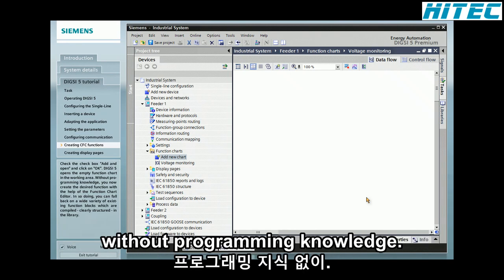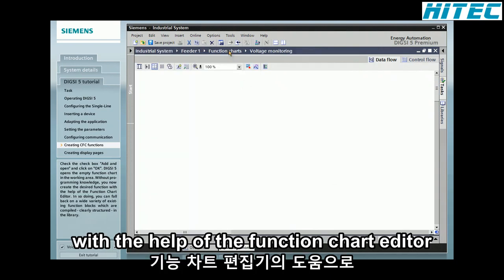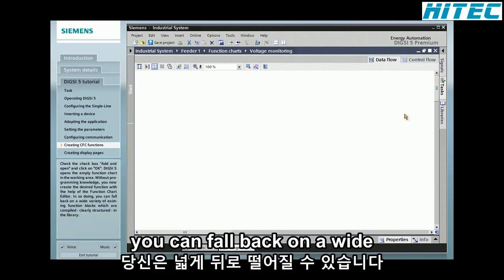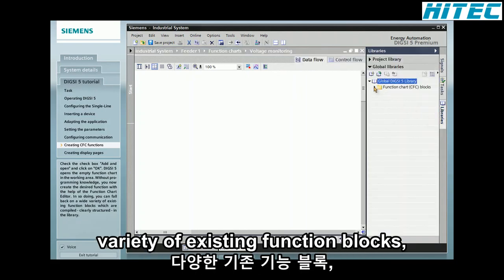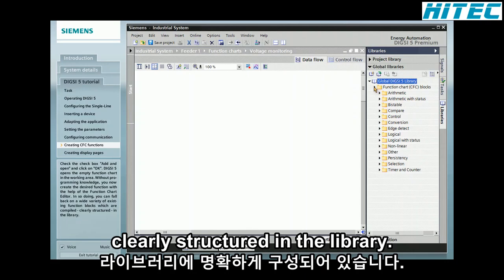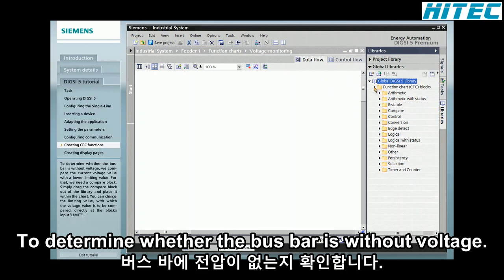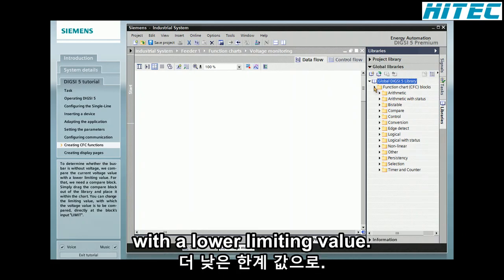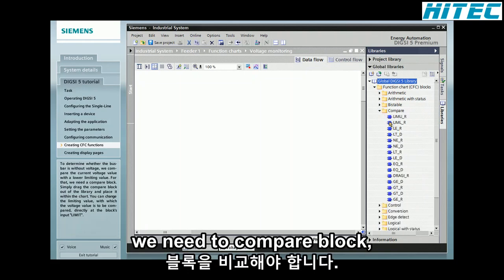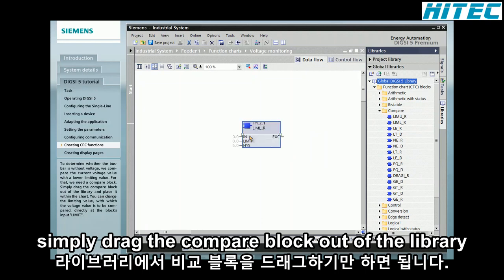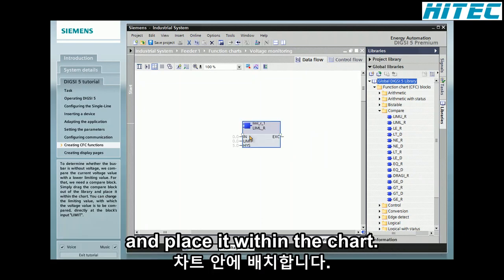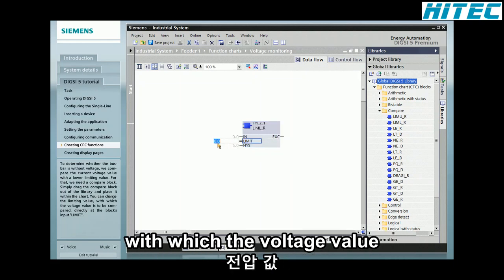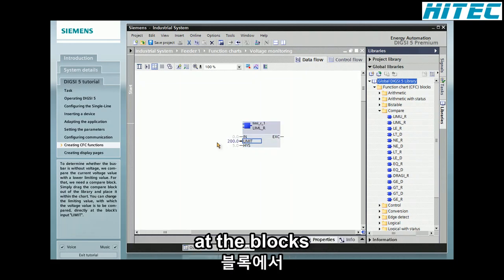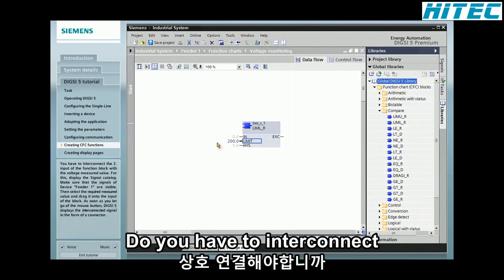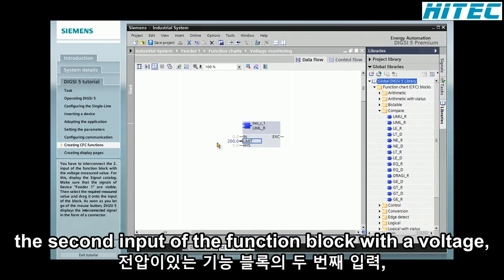Without programming knowledge, you now create the desired function with the help of the function chart editor. In so doing, you can fall back on a wide variety of existing function blocks which are compiled, clearly structured in the library. To determine whether the bus bar is without voltage, we compare the current voltage value with a lower limiting value. For that, we need a compare block. Simply drag the compare block out of the library and place it within the chart. You can change the limiting value with which the voltage value is to be compared directly at the block's input limit. You have to interconnect the second input of the function block with the voltage measured value.